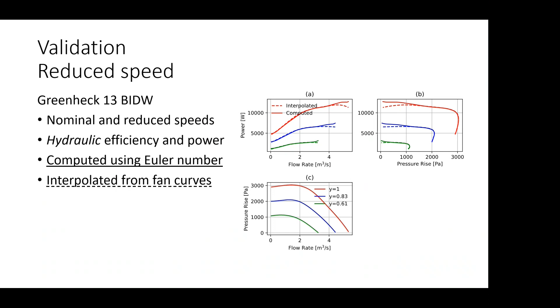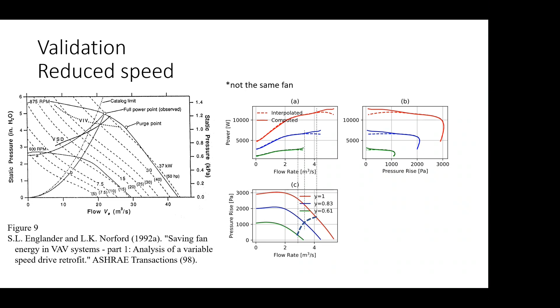If we look at this other figure with static pressure versus flow rate, which is a different fan, we have two important points here. One is the full power point, which is the point where the fan achieves maximum flow rate while maintaining the required pressure. So in operation, the fan is not supposed to go anywhere to the right of this point. We also have another point on this plot, which is the purge point, which is only achieved when all the VAV boxes are fully open. So physically, this fan cannot go anywhere further to the right of this point. Therefore, this lower right region is one this fan is never going to, so having error in this region is not very important for the type of applications that motivated this study.